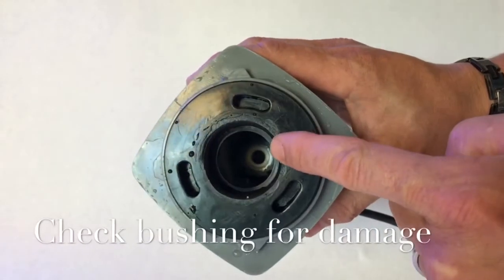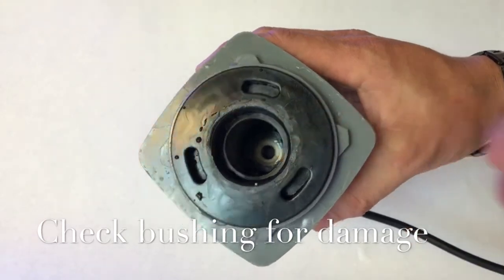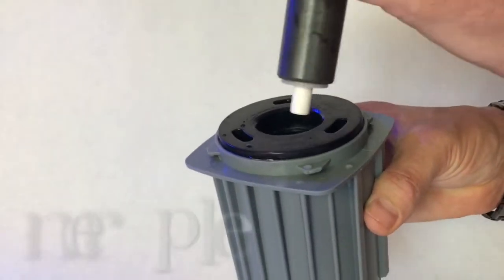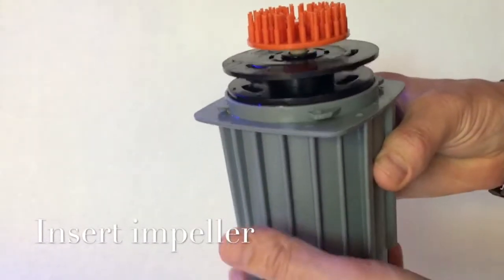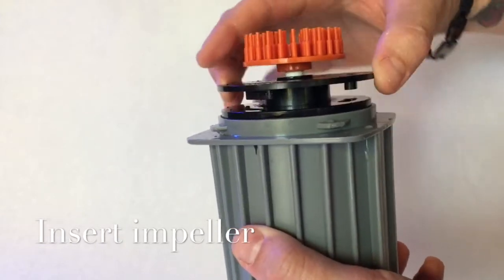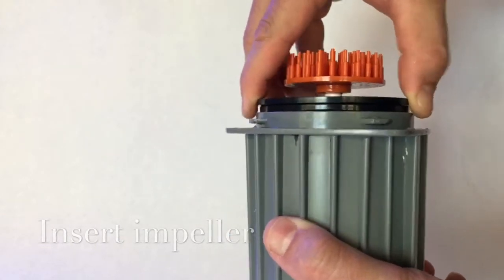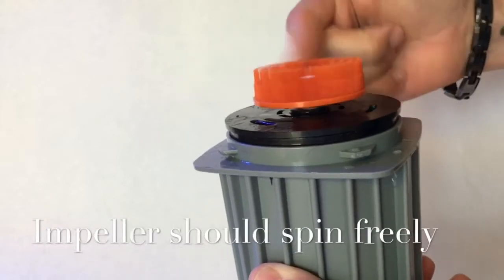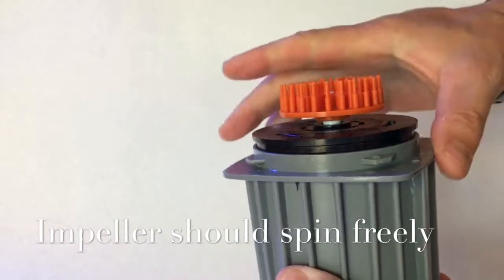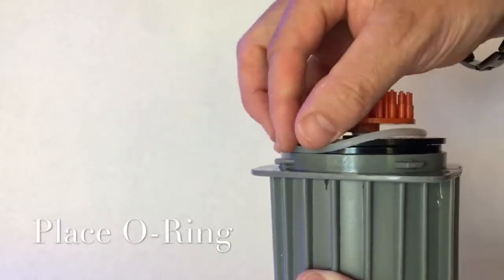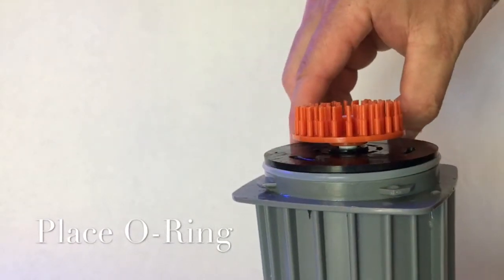Next, let's have a look at the pump body. Inspect the bushing in the back of the pump and ensure that it's not damaged. When inserting the impeller, ensure that the keys line up properly so it can be seated correctly. Make sure that the impeller spins freely once assembled. When inserting the O-ring, the easiest way to do it is to gently squeeze it around front to back with 2 fingers.